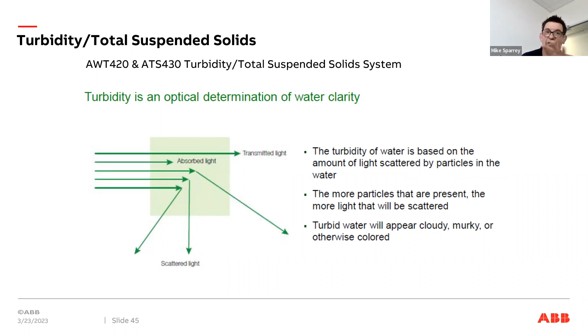So just a couple more slides on the instrument itself. This is about the sensor. We say it's primarily a turbidity instrument, so we are using the nephelometric turbidity method. So we're measuring light scattered at 90 degrees. So yeah, a very industry standard measurement for this.